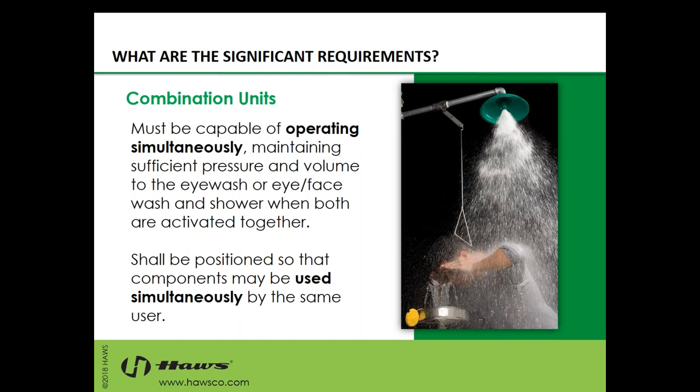Now, the equipment needs to be positioned so that the components can be used simultaneously. You have to be able to use the eyewash or eye face wash and the shower at the same time. Plumbers and contractors, sometimes not versed in ANSI, will position the shower one way, the eyewash the other, and think they're for separate situations, and they're not. They need to be used at the same time.